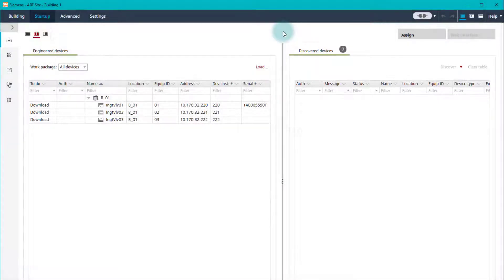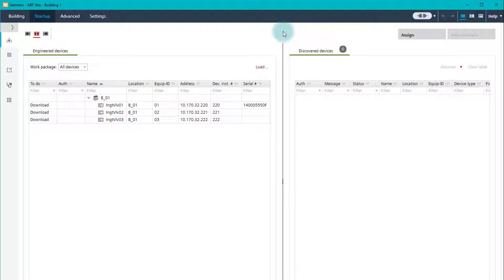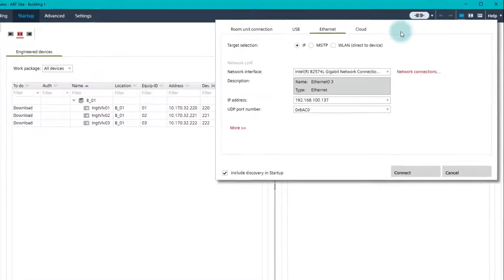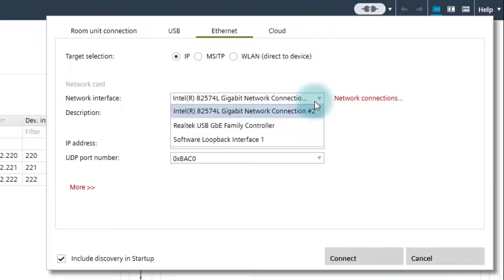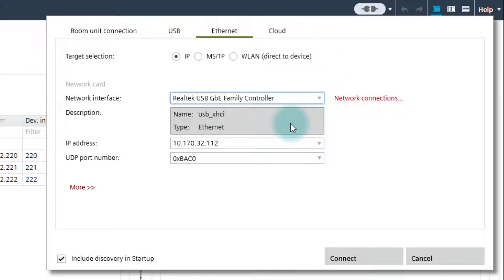To benefit from the mass download, we physically connect ABT Site to the network segment with an RJ45 cable. We click on the Connection Settings button, which allows us to choose the type of connection to the devices. Since we want to discover devices on the network, we select Ethernet. We then choose the network interface, select the correct UDP port number, and click Connect.